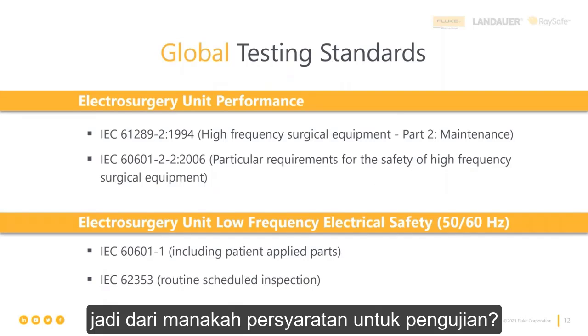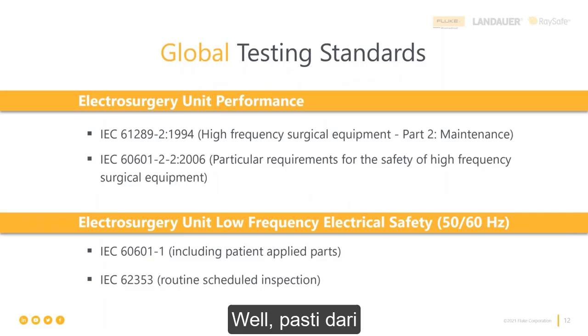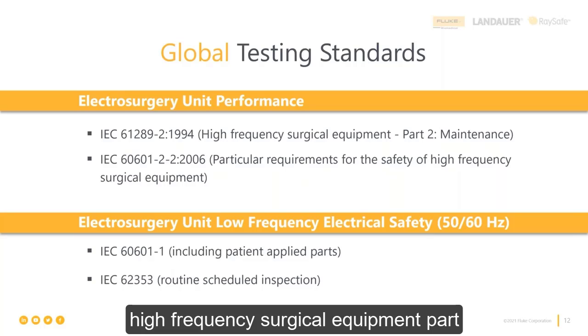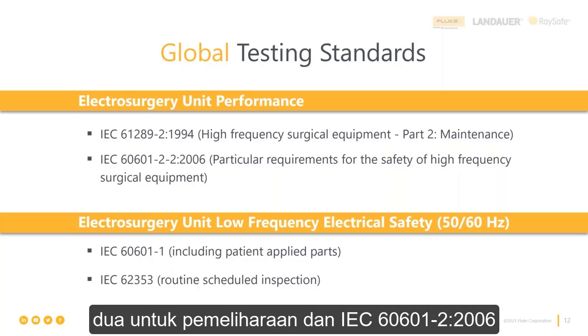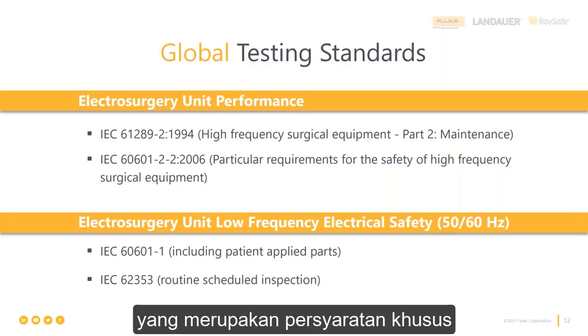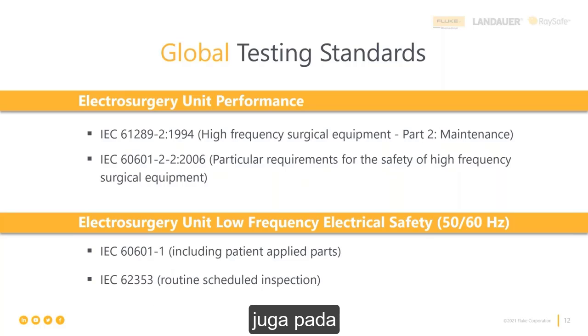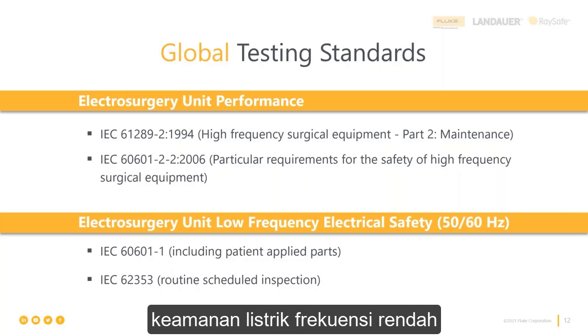So where do the requirements for testing come from? Well, certainly from the international standards. The IEC 61289-2-1994, high frequency surgical equipment, part 2 for maintenance, and the IEC 60601-2-2:2006, which are the particular requirements for safety of high frequency surgical equipment. Also, low frequency electrical safety international standards apply.